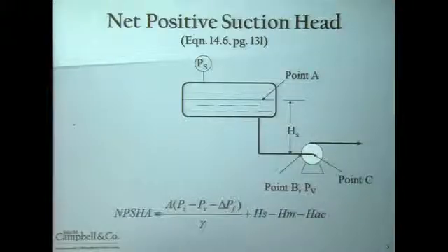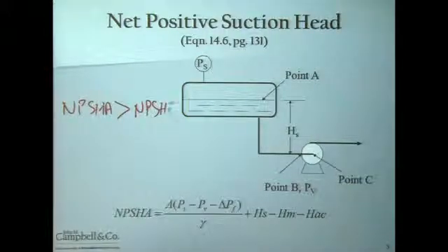Today, what we will do is focus on the concept of net positive suction head available. One of the key points in understanding pumps is that the net positive suction head available must be greater than the net positive suction head required. The net positive suction head required comes from the vendor.